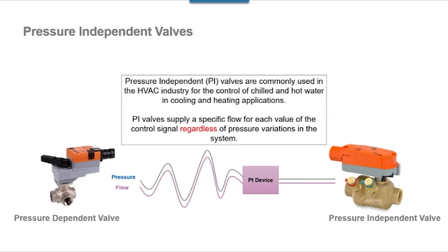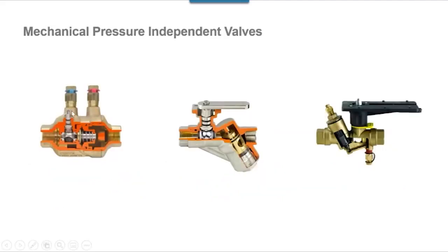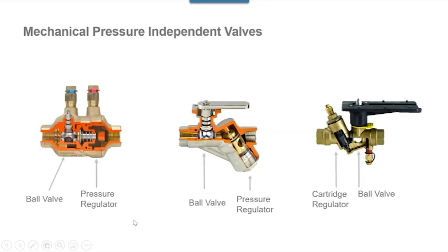PI valves supply a specific flow for each value of the control signal, regardless of the pressure variations in the system. Seems simple enough. So we're going to talk for a moment about the 2 different types of pressure independent valves. On the screen you see right now are some examples of mechanically regulated pressure independent valves. These are all considered 2-chamber devices, because you have a control valve and some type of pressure regulator or cartridge regulator.